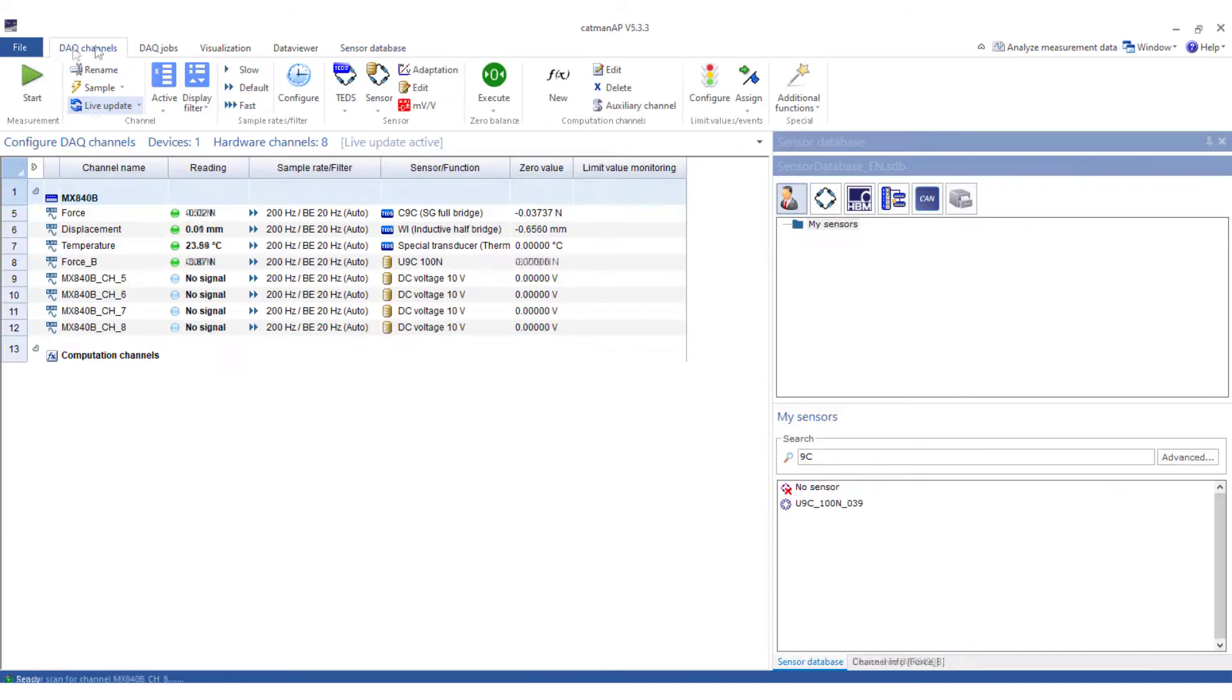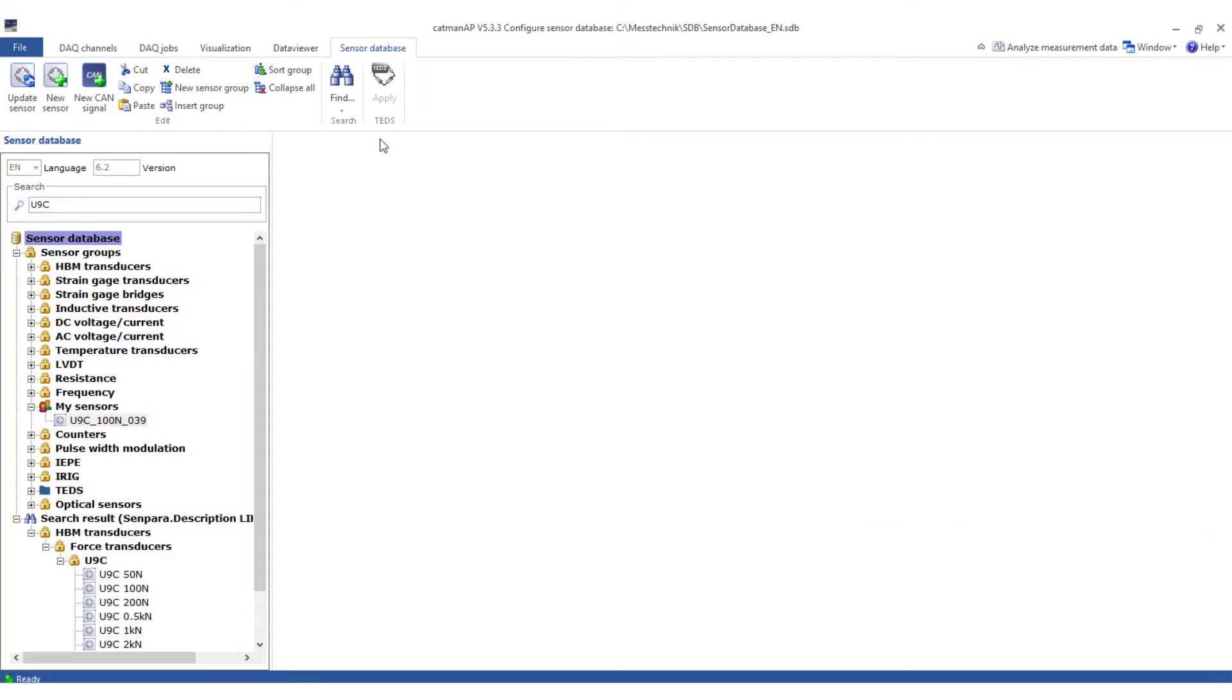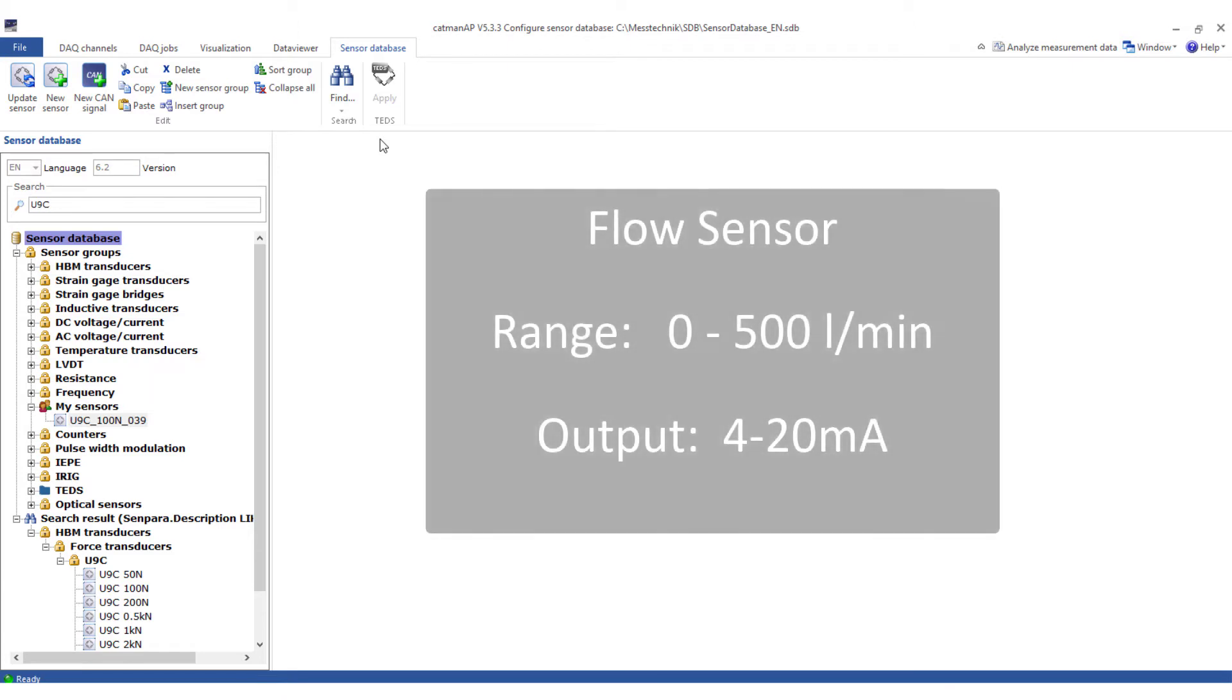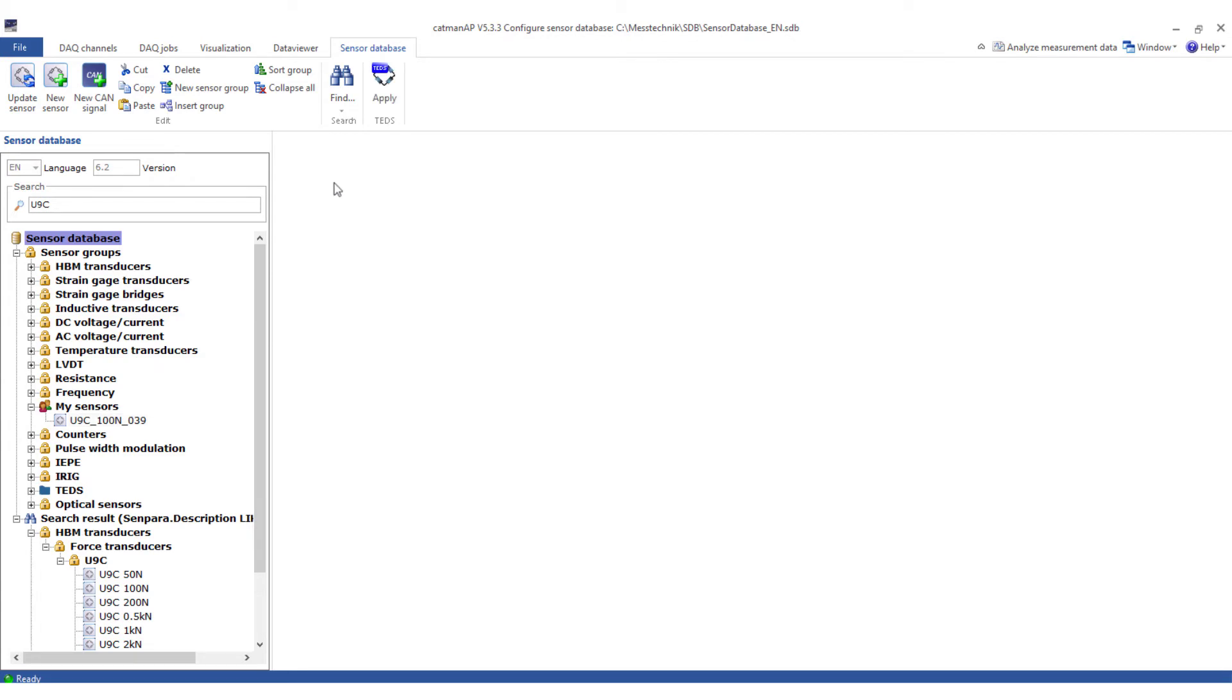I am now also assigning this sensor to the channel. However, you can also enter sensors for which no direct template exists. My new sensor is a flow sensor that provides a 4 to 20 milliamp signal at the output and has a measuring range of 500 liters per minute. So at 0 liters per minute the sensor delivers 4 milliamps and at 500 liters per minute the sensor delivers 20 milliamps.